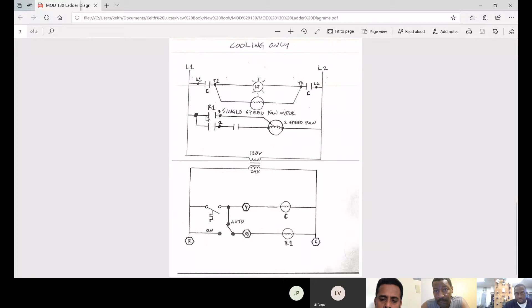So that part is done. And then really quick. So we had this is done, L1 to terminal 1. Now we got to go from terminal 3 to high speed. So our terminal 3 is right here. Our high speed is going to be the black wire on our 2-speed motor. So I'm going to do that right here. Terminal 3. And again, it's marked. If you were here, you could see where terminal 3 was. They're all marked. It's just really small writing, but it's on there.